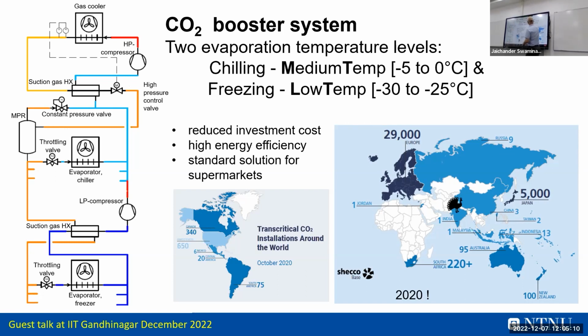And typically we do -5 to 0 for the chilling part in the evaporator. And the good thing is, previously you needed to make the room at 2, 3, 4 degrees. You needed to go to -10 in the evaporation. Means you have a lot of moisture on the evaporator, defrost all the time, a lot of heat in and out, and it takes a lot of energy.